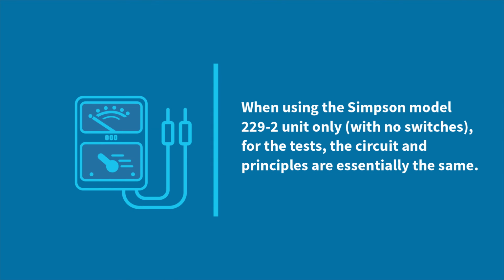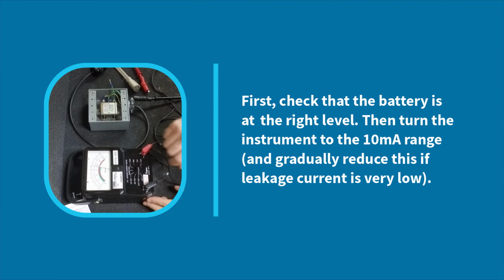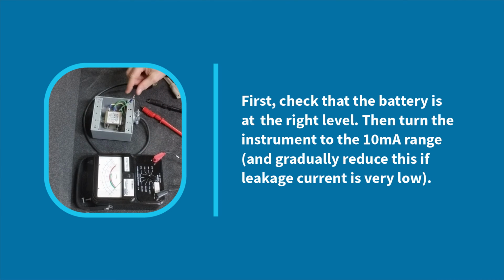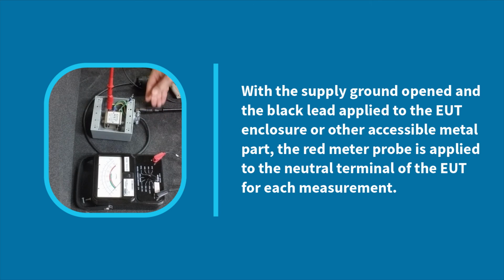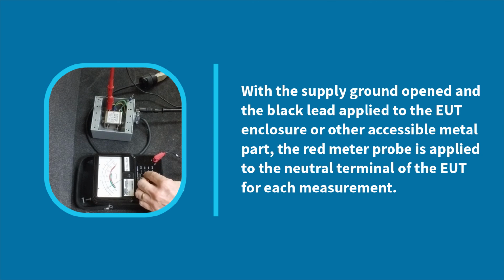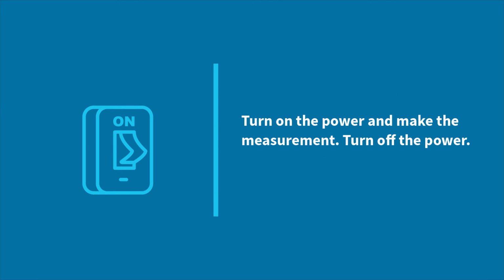When using the Simpson Model 229-2 unit only with no switches for the tests, the circuit and principles are essentially the same. First, check that the battery is at the right level. Then turn the instrument to the 10 mA range and gradually reduce this if leakage current is very low. With the supply ground opened and the black lead applied to the EUT enclosure or other accessible metal part, the red meter probe is applied to the neutral terminal of the EUT for each measurement. Turn on the power and make the measurement.